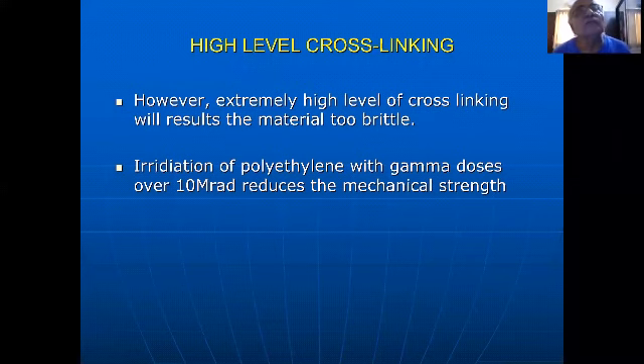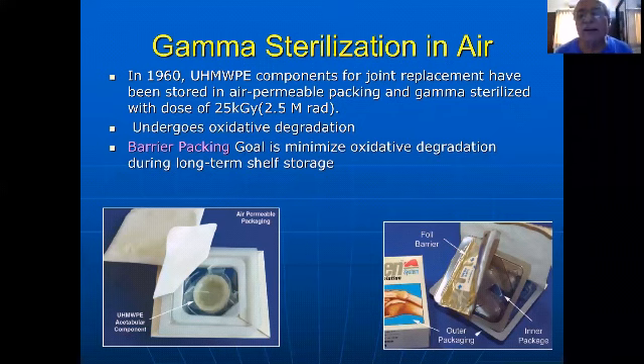So then how do we sterilize this material once it is all manufactured in the factory? We used to store this material in air permeable packing at that time and gamma sterilize it in the air. We didn't do it in a laminar flow, and we didn't do it in a nitrogen atmosphere. Because air was trapped in this material, after keeping it on the shelf, it started undergoing oxidation degeneration. After 2 to 3 years, it becomes so brittle that it gets fractured, and the wear rate was very high. We were not aware of this.